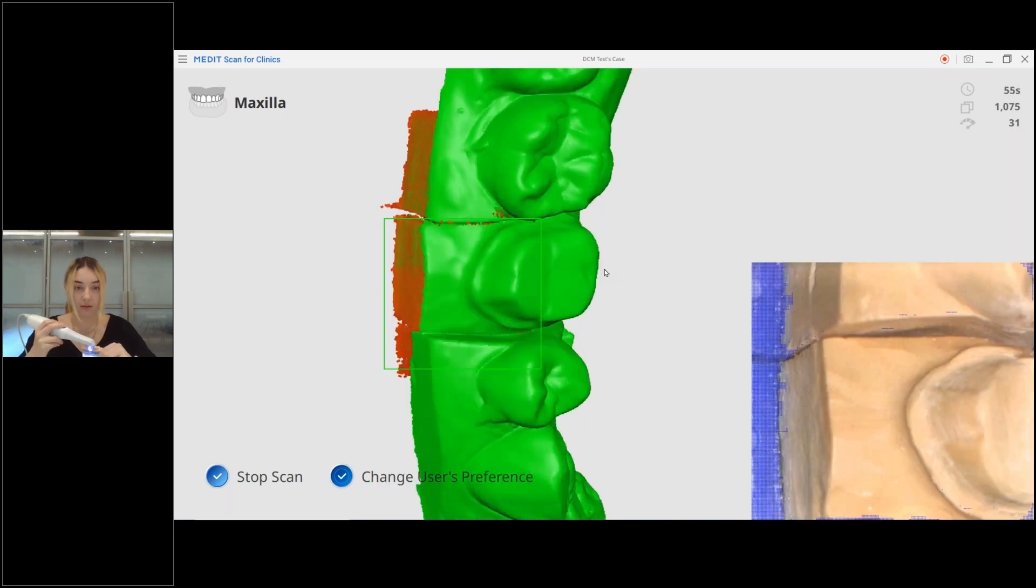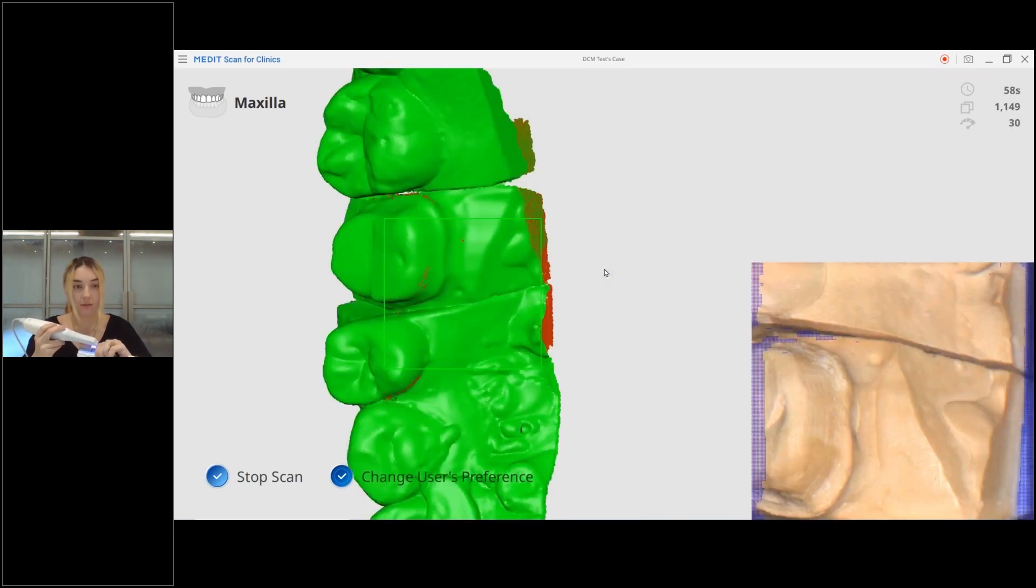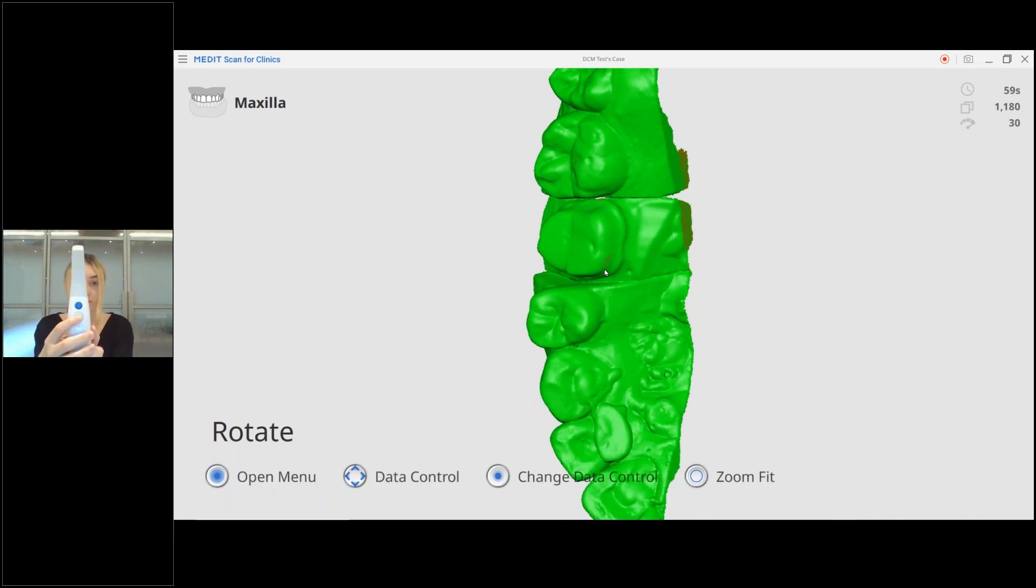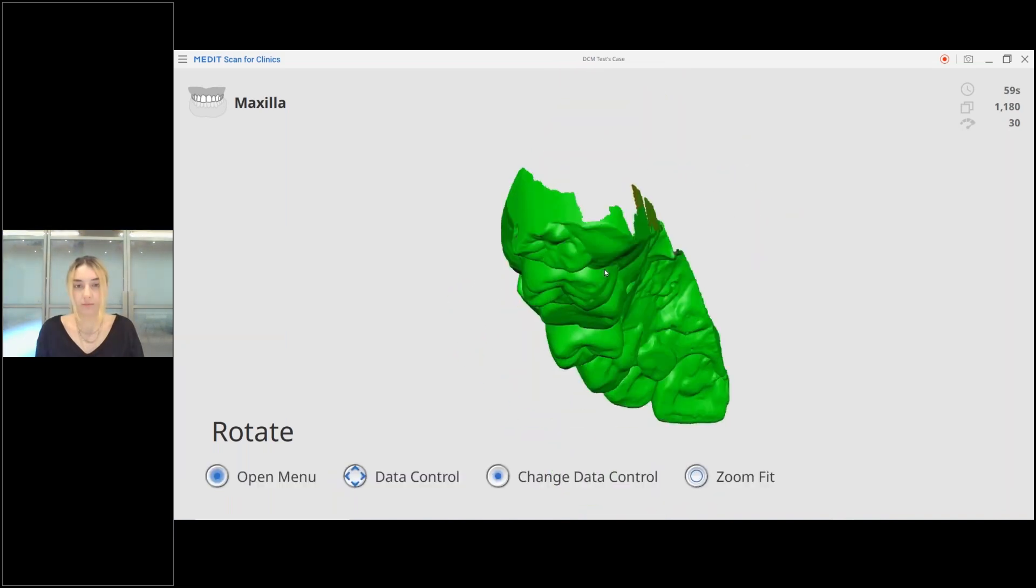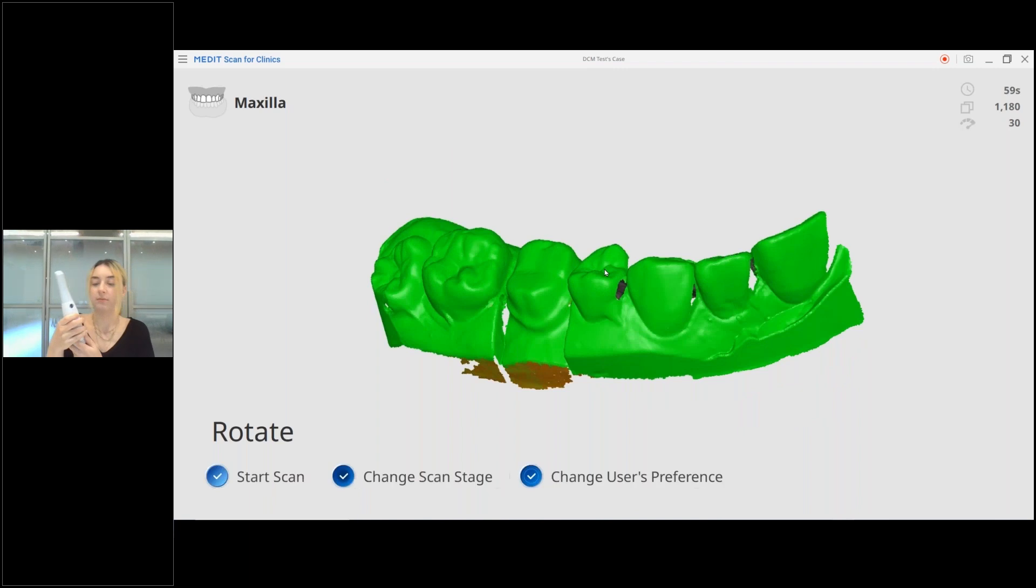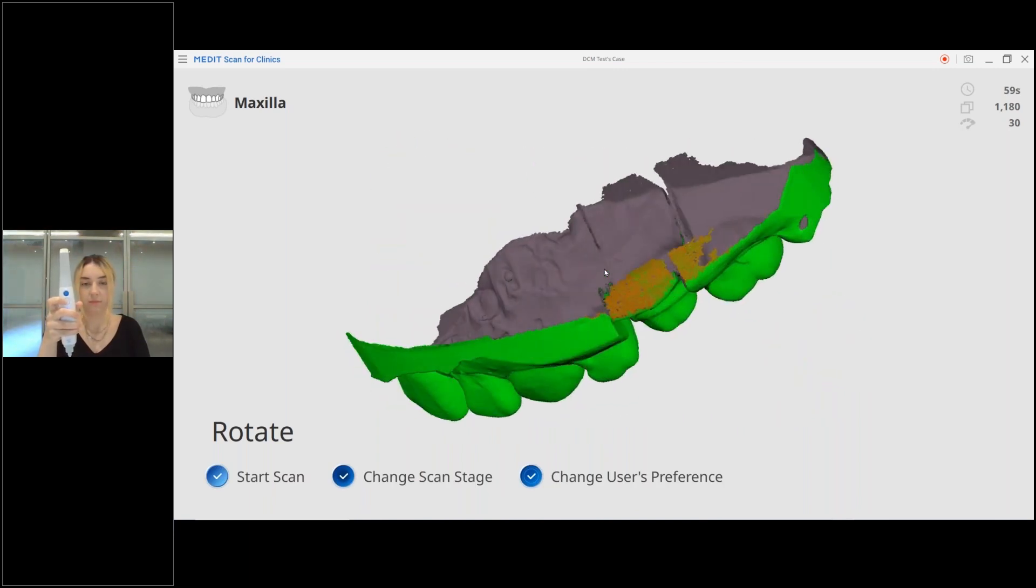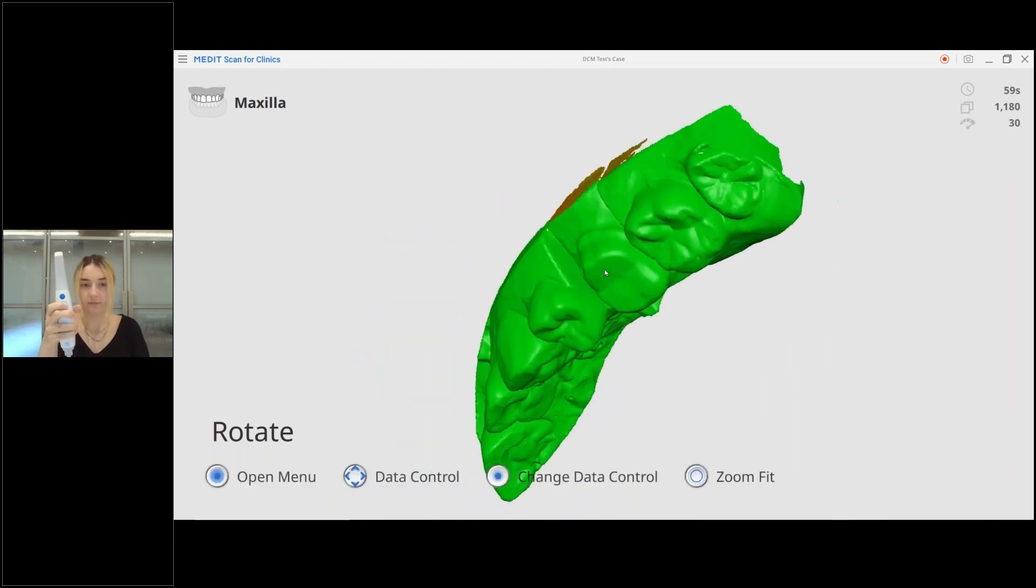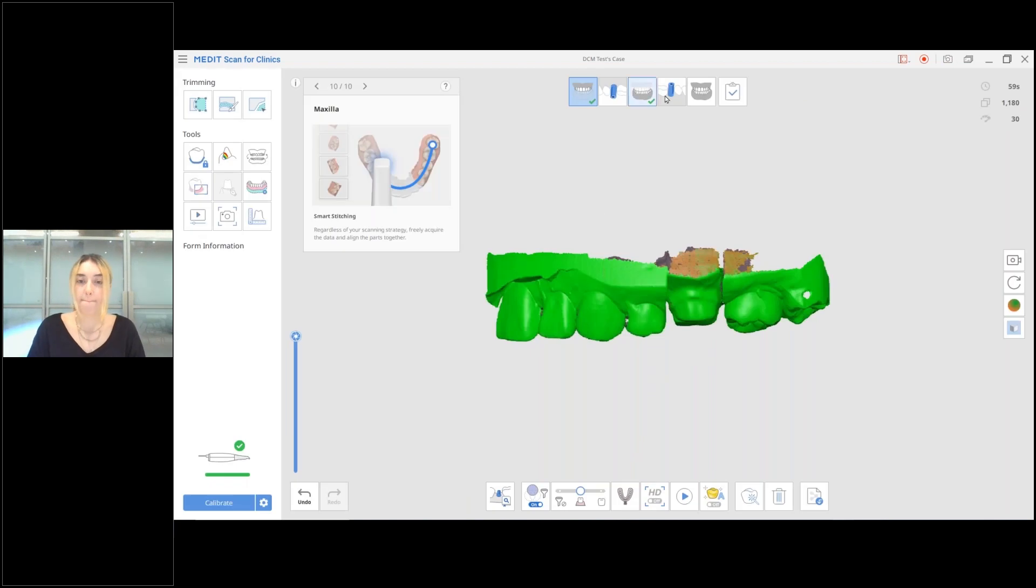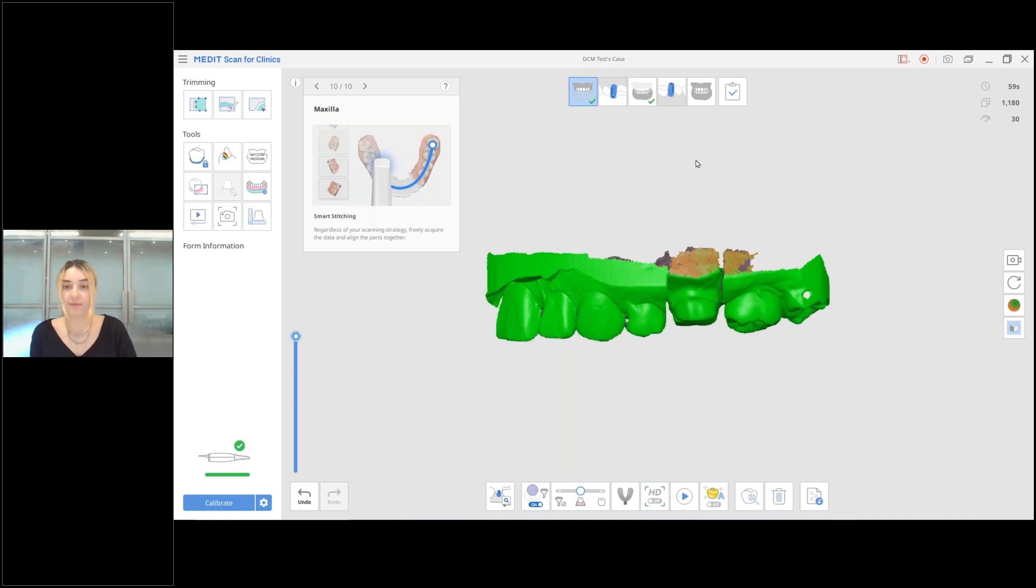In order to get into remote control mode, remember that this is a feature that's significant and exclusive to the i700. In order to get into remote control mode, she's going to hold that white button right in the center for a long hold and that opens up remote control mode. You'll see that in remote control mode a lot of the icons are gone, it's just the model. From there she can actually use the button on the scanner to rotate, to pan, and to zoom in and out. It just depends on if it's a long hold or if it's a short hold in order to switch between rotate, pan, and zoom. Basic scan mode is good with i500 and i700, but the i700 does allow you to go into remote control mode and not go back to your keyboard or your mouse while you're scanning, so it's pretty convenient.